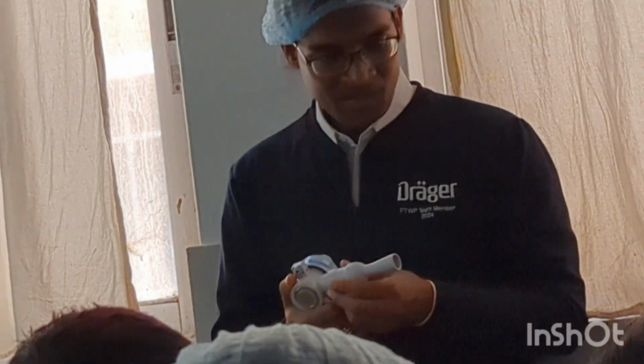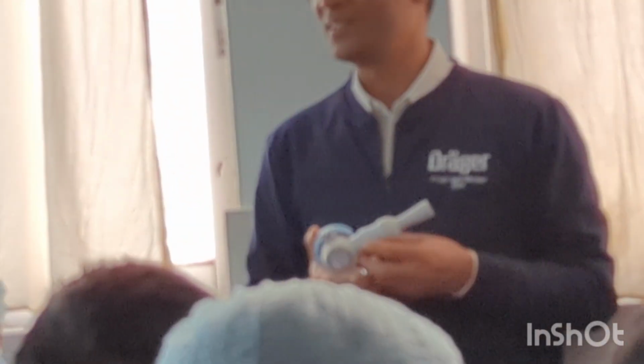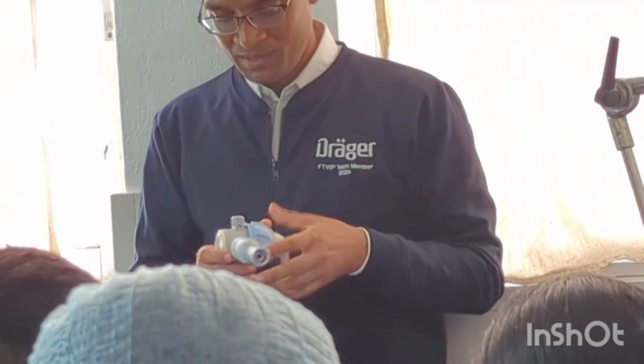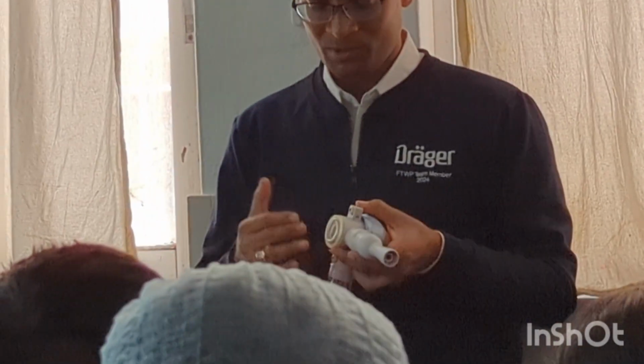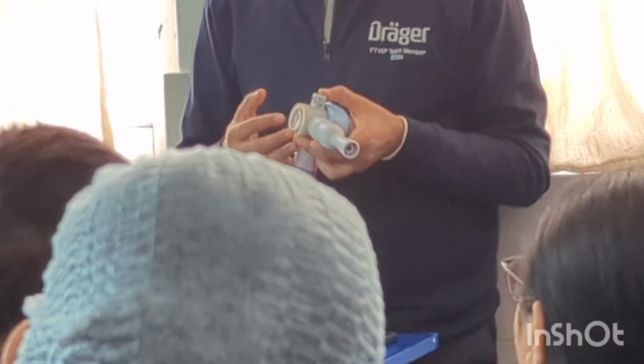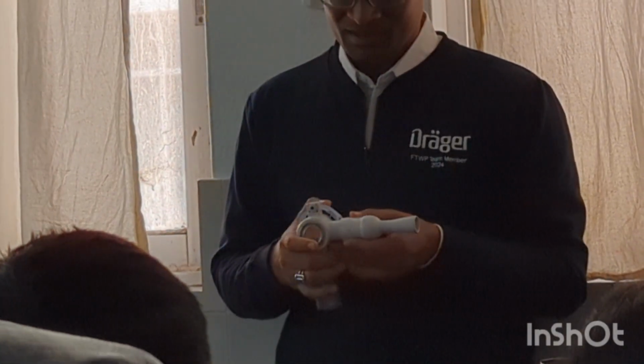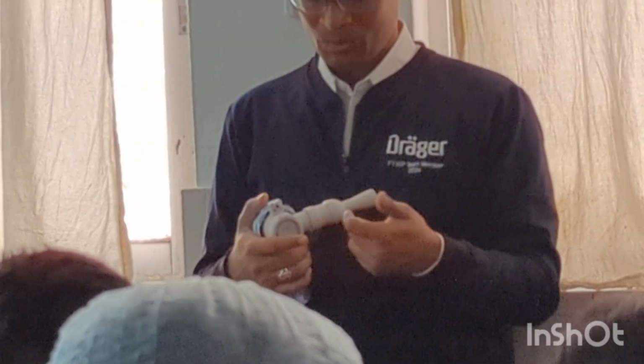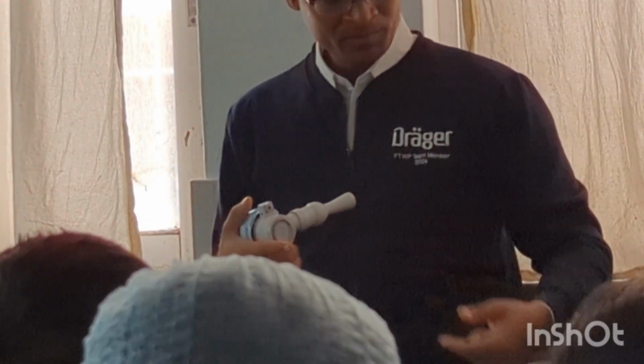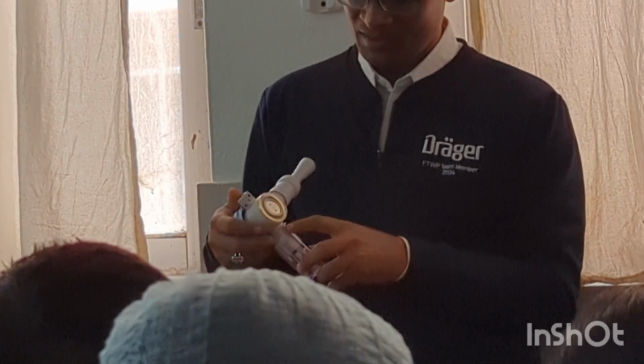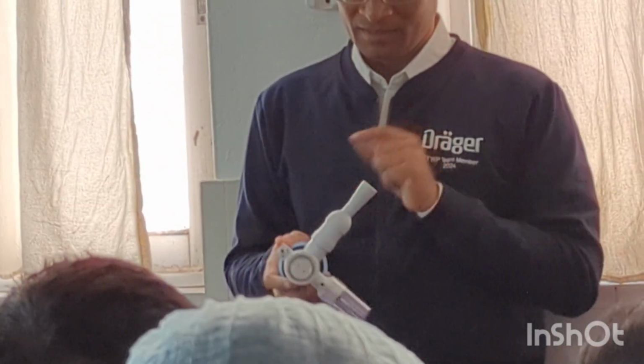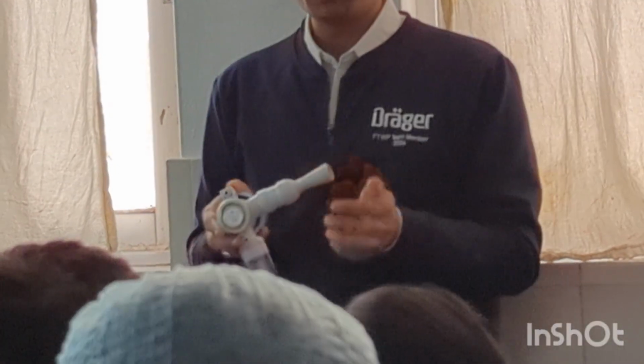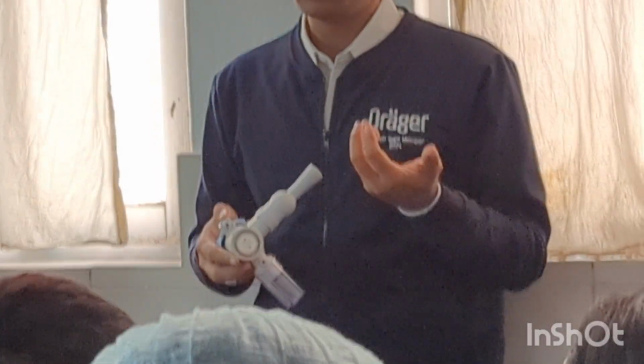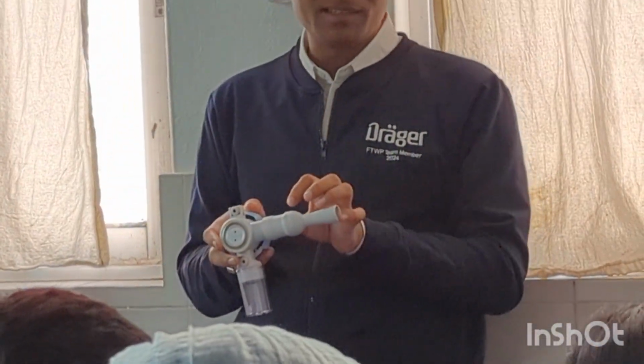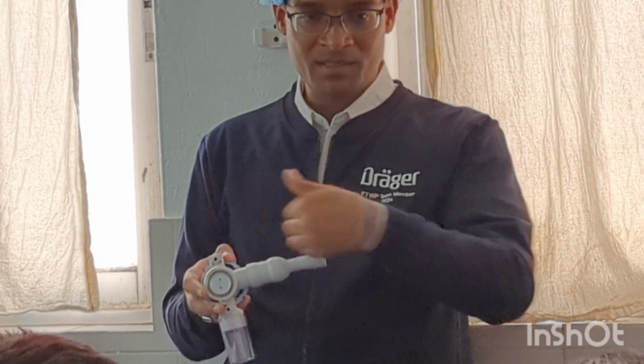And that's just one more feature I will show. It's not just a simple expiration valve here. There is an ejector over here. If you know about the Babylog 8000, it has drivers like ejectors. What does it normally do during high frequency ventilation, for active expiration? High frequency is known for active inhalation and active exhalation. There will be a venturi inside this, and because of that venturi there will always be a continuous flow coming through this ventilator. You can see here, it will pass through this. There is a venturi as well as a silencer, because if there is a very high flow passing through this, you would hear a lot of noise. So they have also given a silencer, so you will not hear any noise even when there is a flow passing through.